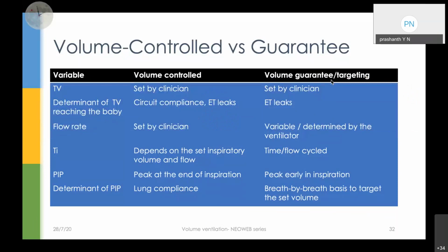The flow rate is set by the clinician, so we can decide how much flow the baby has to get. In volume guarantee, since it's a dynamic process, it is variable and determined by the ventilator, because it has become intelligent now. So what about the inspiratory time? In volume control, inspiratory time depends on the set inspiratory volume and flow. It doesn't look at anything else; it just looks at the volume which has to go, no matter what. But in volume guarantee, most often we combine it with the pressure control modes, like an assist control mode, where it could be time or flow cycled.